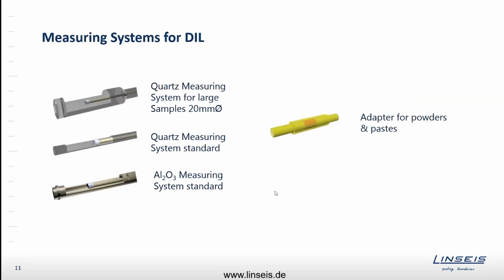So far about the detection systems. And then we have measuring systems that are very flexible. The sample holders and the push rods can be made of different materials. Our sample holders usually are made of quartz. For higher and lower temperatures, we have different systems. For high temperatures, we have aluminum oxide or alumina systems, where the push rod and the sample holder are made out of alumina. We also have systems made of tungsten and of quartz. If a customer needs a special setup and a special material, we can also design these sample holders and rods out of special materials that customers request.